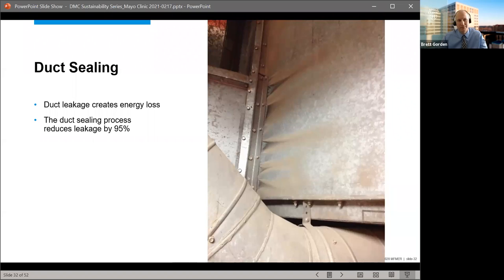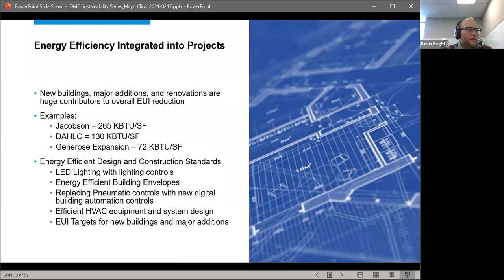This process has resulted in reduced leakage by 95%. Anecdotally, we did this in the Guggenheim building, a 22-story lab and research facility with some really large air handling equipment. Just by sealing all the supply ductwork mains in that building, we captured back about 42,000 CFM of supply air that we did not need to supply. That meant we captured back almost a whole air handling unit, creating redundancy for us, which increases reliability on top of all the energy savings.